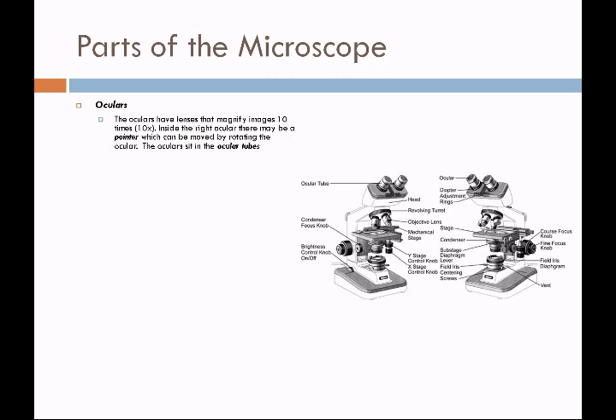Inside the right ocular, there may be a pointer. It's going to appear as a line, and it can be moved by rotating the ocular. The ocular sits in an ocular tube. Below the ocular is a diopter adjustment ring. This ring is used to accommodate the fact that both of your eyes may not be focused the same. Most of you will find that you don't have to do any adjustments, that your eyes are pretty close in their ability to magnify.